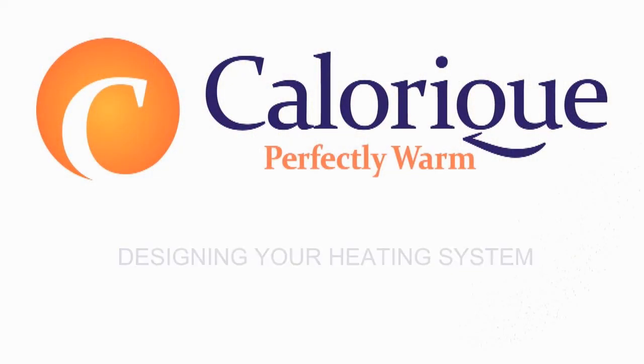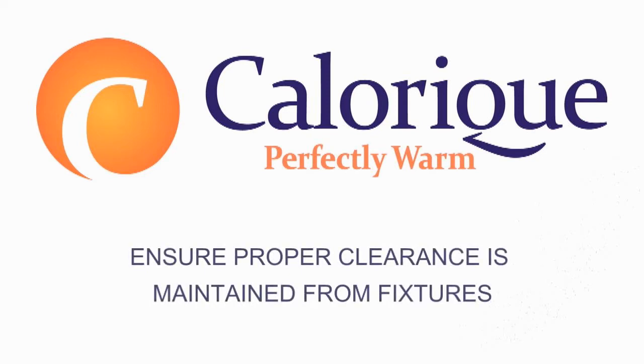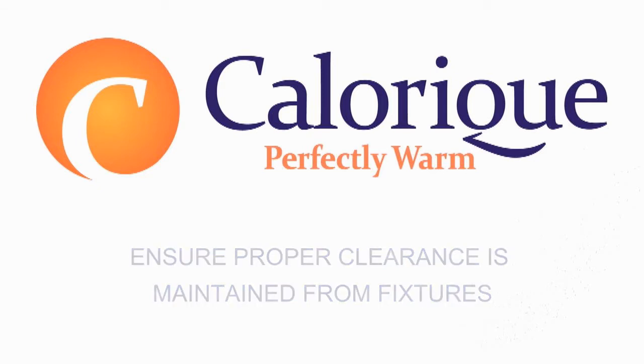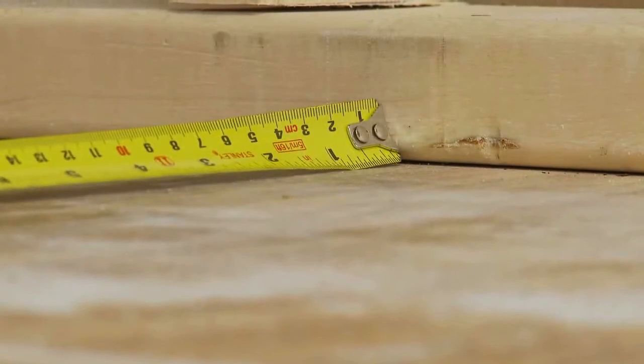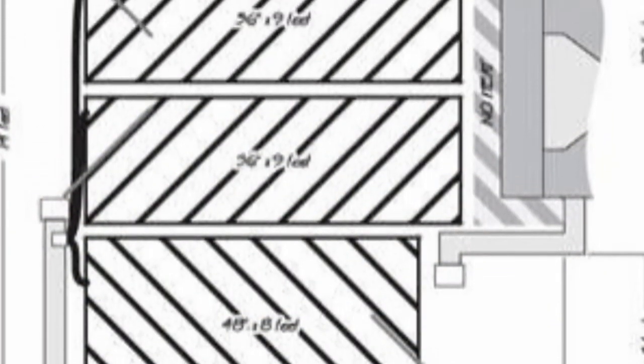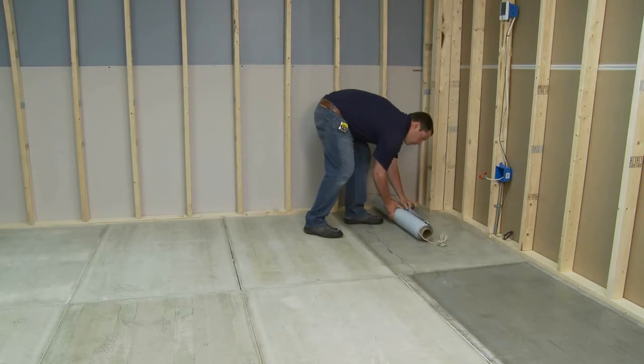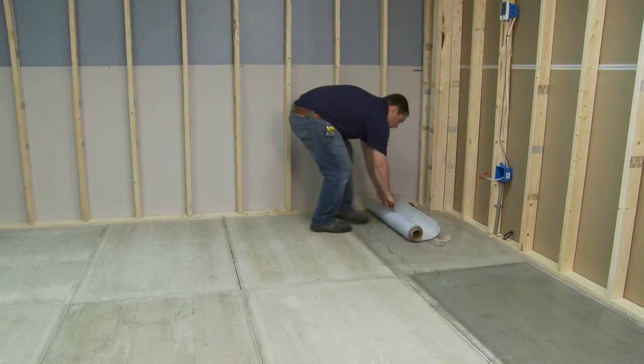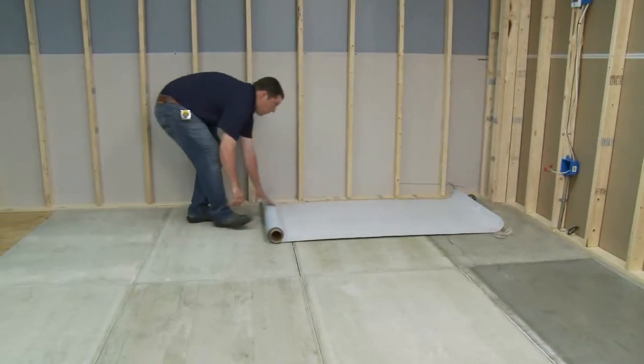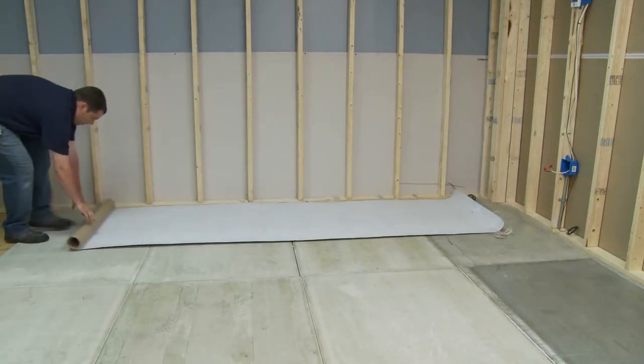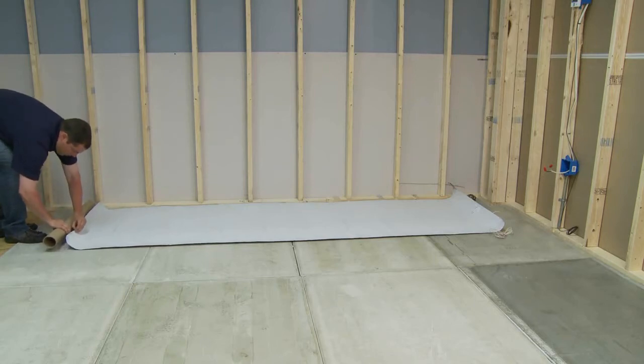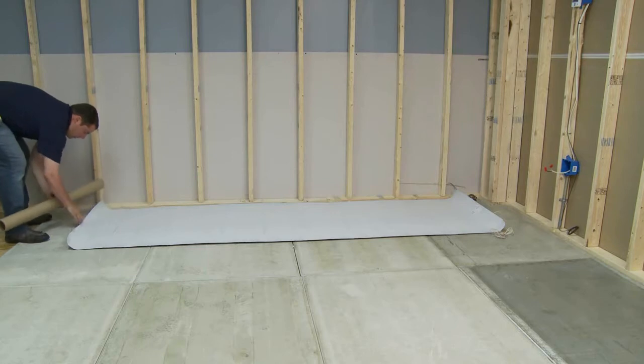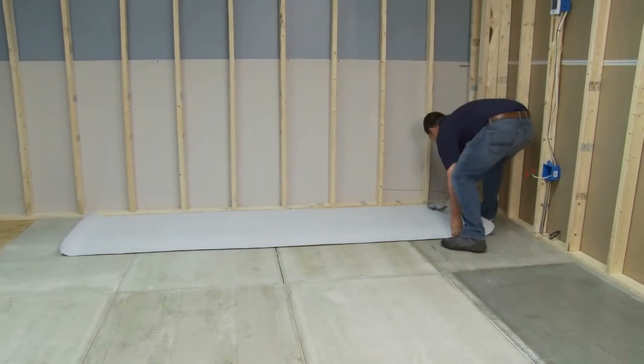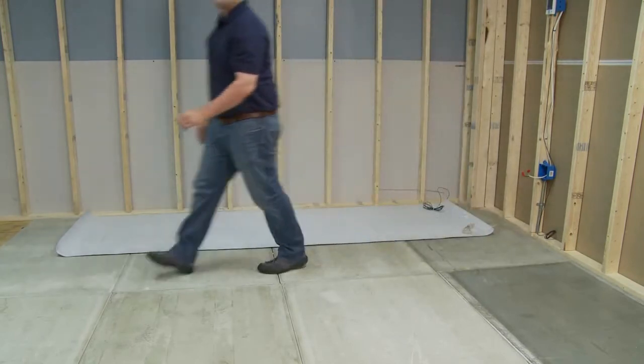Designing your heating system. When designing the heating system, care must be taken to ensure that proper clearance is maintained from fixtures which may be part of the floor. To select the proper size heating mat, measure the area to be heated and determine the heating mat widths and lengths from wall to wall. Accurate dimensions are required for the proper size selection or for custom mats to be ordered and fabricated. It is important to allow up to 6 inches of clearance around the perimeter of the room and from any baseboard heating or permanent fixtures to allow the mats to fit without touching adjacent vertical surfaces or overlapping.